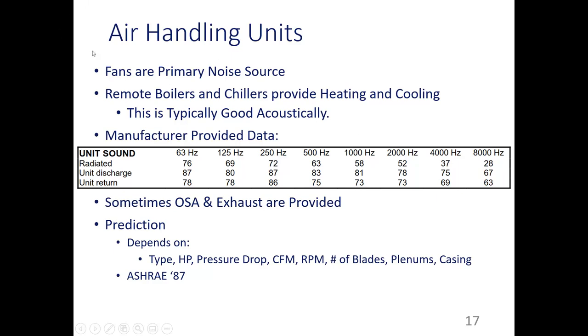A lot of times these are sitting outside, so the outside air and the exhaust are just going to be openings inside of the unit. There's like a louver there, a grill, but it's for the most part open. Sometimes they'll put these in attic spaces, and then they need to duct over the outside air and the exhaust. They need to duct that over to a louver in the building. So in that case, you'd want to go with the sound power level for the outside air and the exhaust.